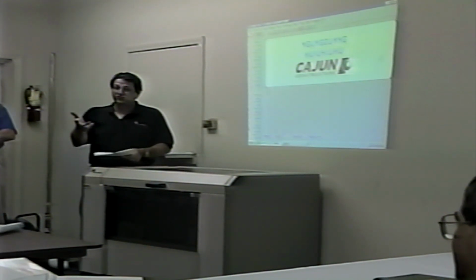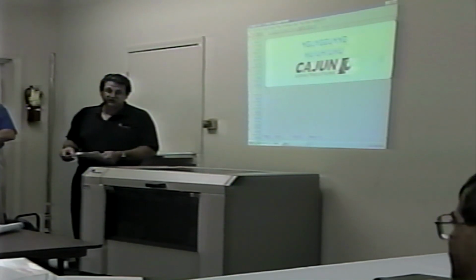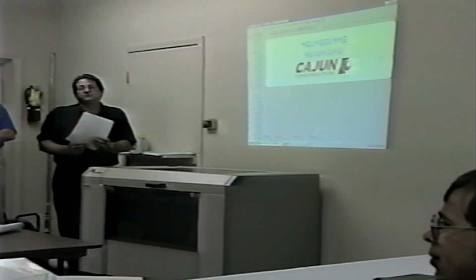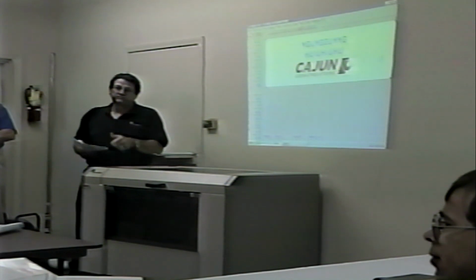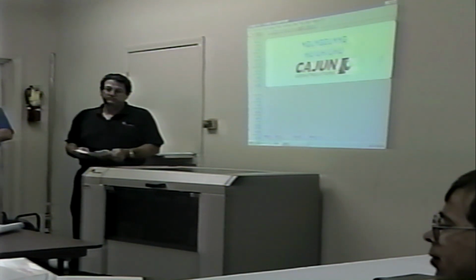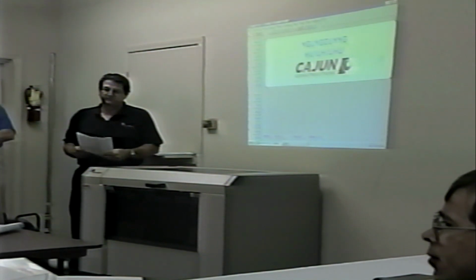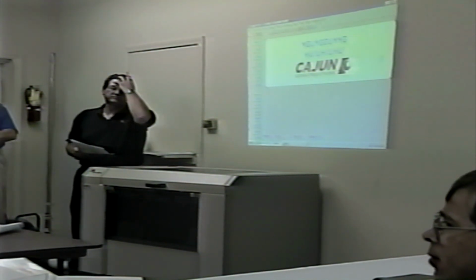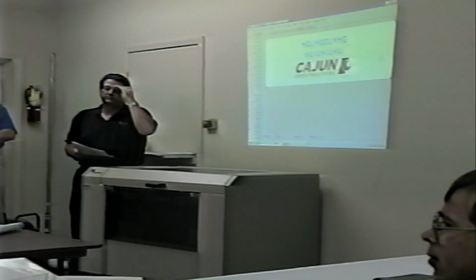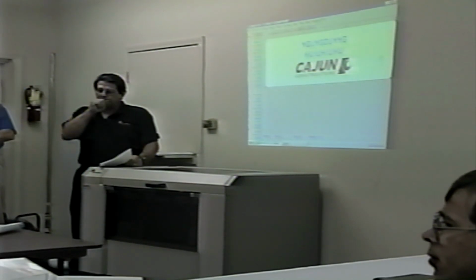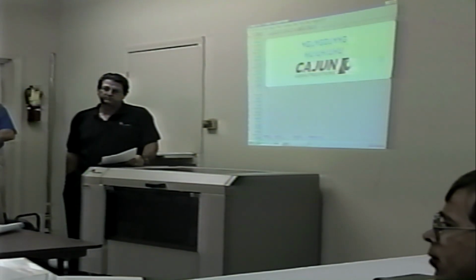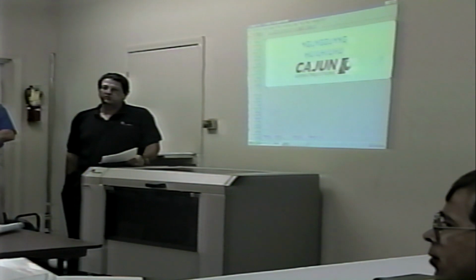Joe, you've installed an awful lot of lasers. Have you had any problems? The only thing I've run into is that they try to run too many rotary machines with the older rotary tables real close to it. It puts out RF interference, and sometimes the servo motors mess up. All I've done is move their table to the other side of the building and it takes care of it. But I had that same thing happen with a System 100 big motor next to it. Yeah, well, those motors scream RF.